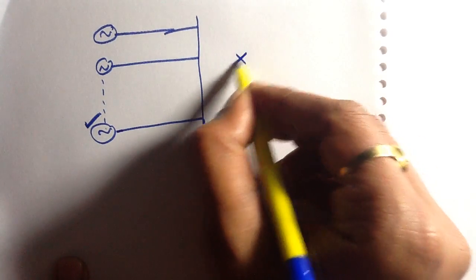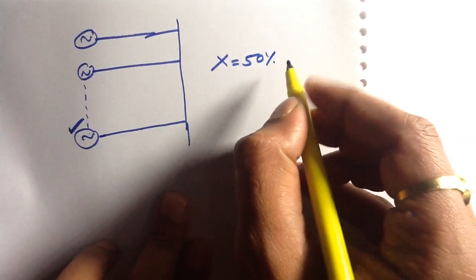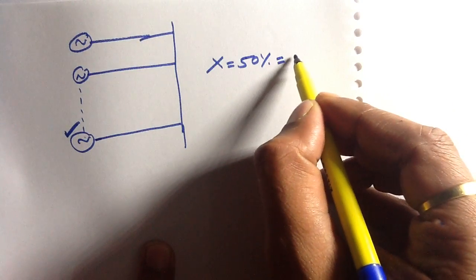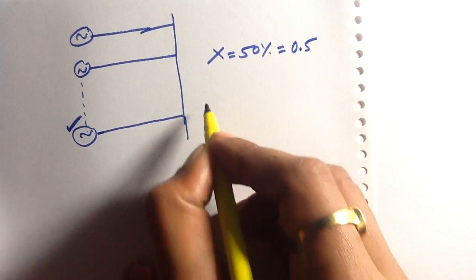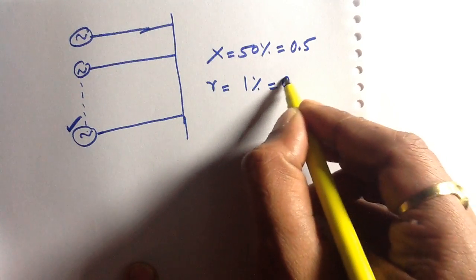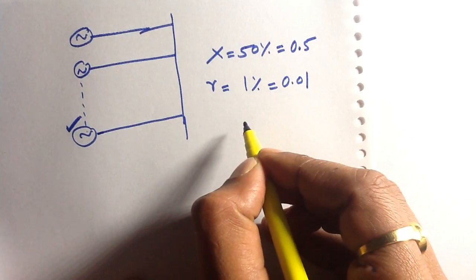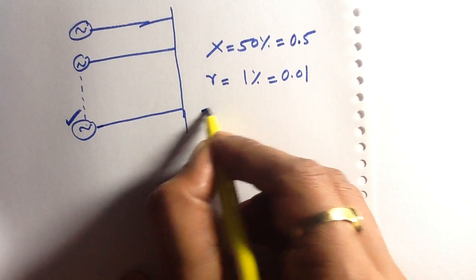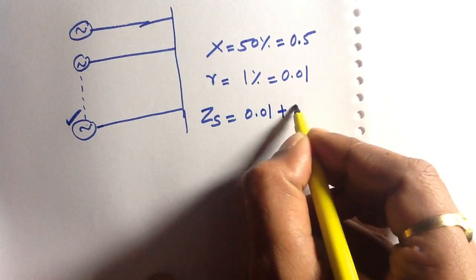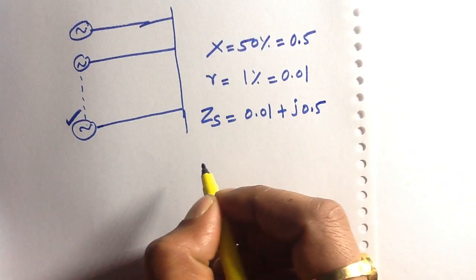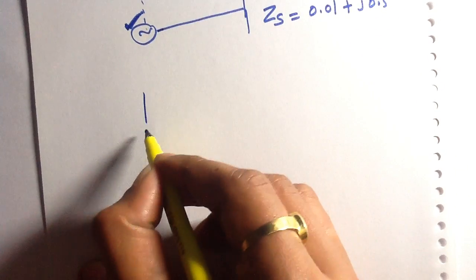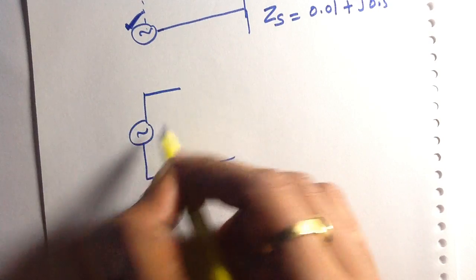The reactance of the alternator is 50%; converting this percentage value to per-unit gives 0.5 per unit. The resistance is 1%, which converts to 0.01 per unit. Therefore, the per-unit value of the synchronous impedance Z_S equals 0.01 + j0.5 per unit.